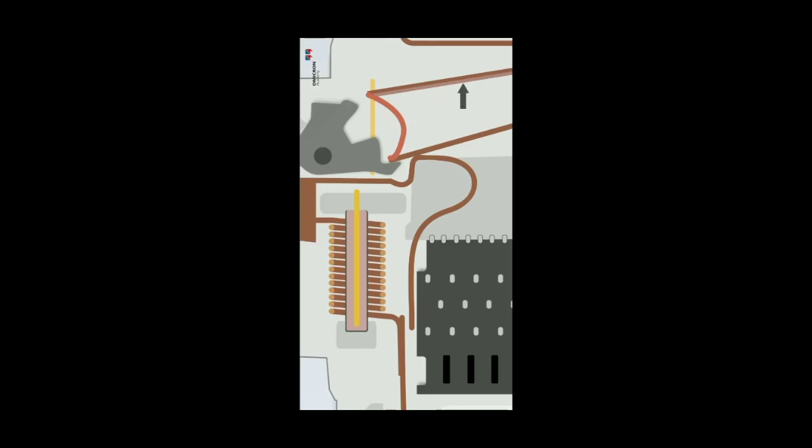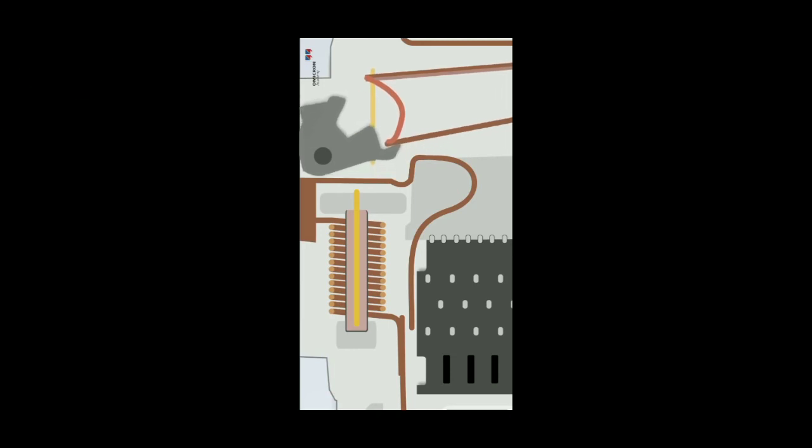The higher the amplitude of the overcurrent, the faster an MCB must trip. This is achieved with a metallic element consisting of 2 different metals, which are heated up by the current flow. The 2 metals expand at different rates while they're heating up. An overcurrent that is present long enough will eventually activate the breaking element.